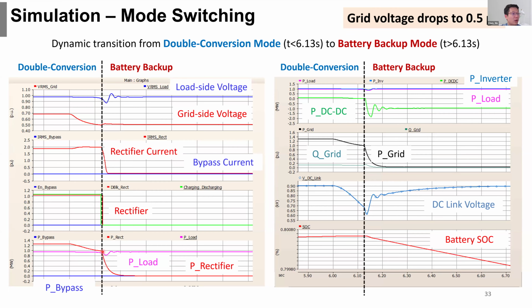Looking at the power, you can see the bypass power is still 0. The rectifier dropped from close to 1 per unit to 0, because in this case the power is fully from the battery, but the load is still maintained close to 1 per unit.